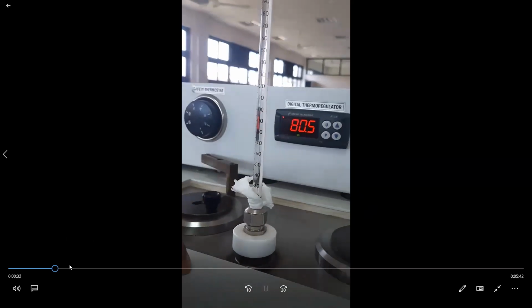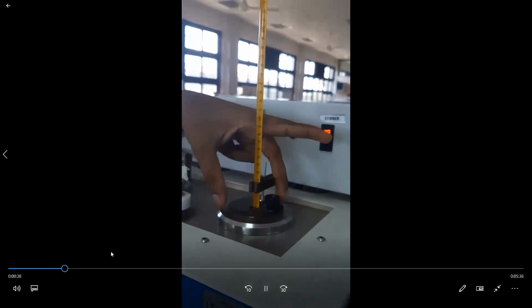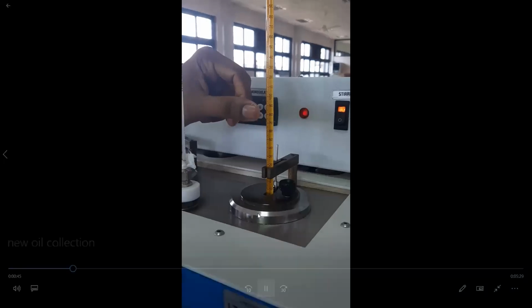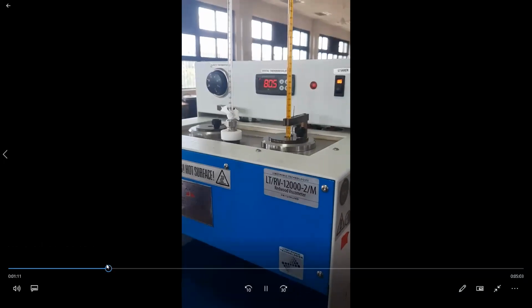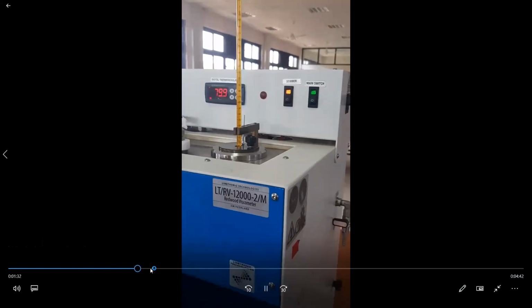This is the water temperature. In that water tank, this oil sample is in the middle of the water tank. You can see it is between 75 and 80, like 76 degrees Celsius. Why is the temperature lesser than that of the water? Because it took some time to transfer the heat from water to sample oil. So we should give it some time.